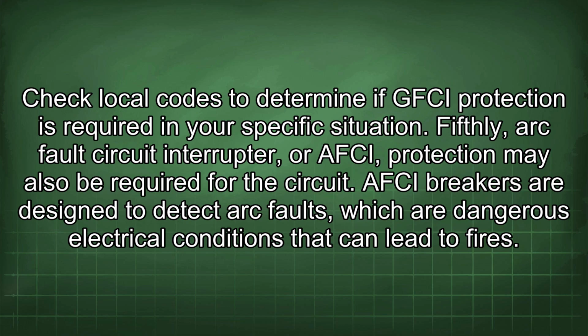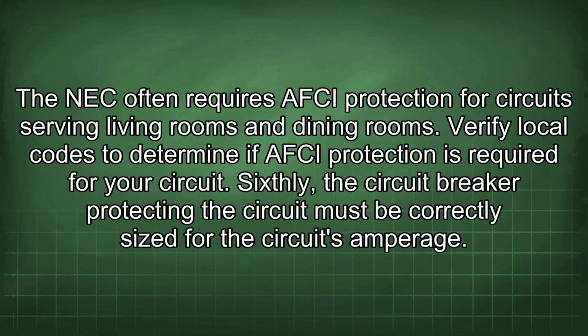Fifthly, arc fault circuit interrupter, or AFCI, protection may also be required for the circuit. AFCI breakers are designed to detect arc faults, which are dangerous electrical conditions that can lead to fires. The NEC often requires AFCI protection for circuits serving living rooms and dining rooms. Verify local codes to determine if AFCI protection is required for your circuit.